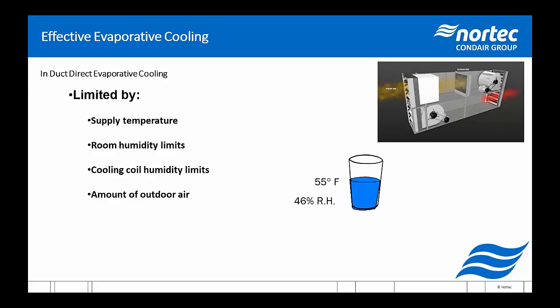So the in-duct evaporative cooling is limited by supply air temperature. Obviously, we can only fit so much water in 55 degrees, as well as the room humidity limits and the cooling coil humidity limits, as well as the amount of outdoor air. So a lot of the same problems, a lot of the same limitations, but one extra one where the supply air temperature is lower than the room temperature.